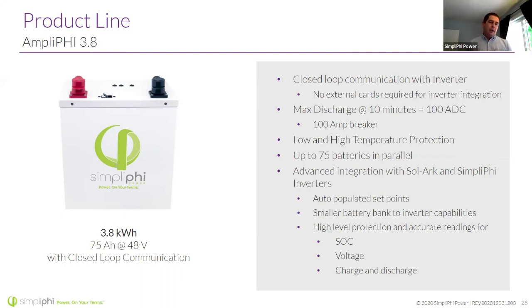If we are in freezing conditions, it's really bad to recharge the battery. If you can slow that charge rate down, it's not as bad. So what the AmpliPHI battery can do is communicate to the inverter its cell temperature. It's important to differentiate between ambient temperature, which might be freezing, the air temperature within a battery cabinet, and the temperature of the cells themselves, which might be warmer still. So the battery accurately communicates its internal temperature, and through an algorithm, the inverter knows it can charge or discharge at a reduced rate.